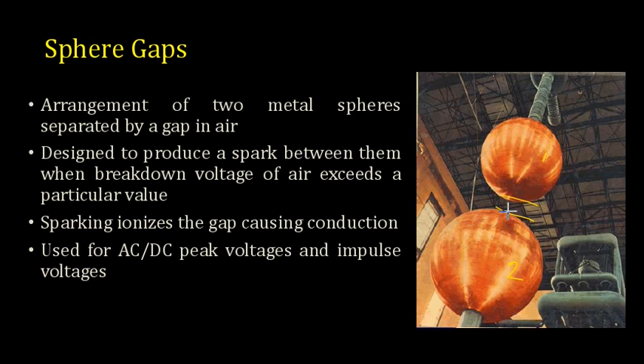So once the applied voltage exceeds the breakdown voltage of air, that is, under normal conditions, 20 kV peak per centimeter, there will be a flashover across this particular sphere gap. So you can identify the voltage at which the flashover occurs, and that voltage can be measured. By adjusting the gap distance as well as the diameter of the gap, we can use this arrangement for measuring different levels of voltages. It can also be used for measuring AC, DC peak voltages as well as impulse voltages.